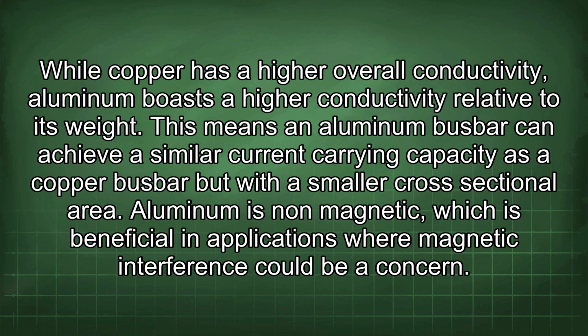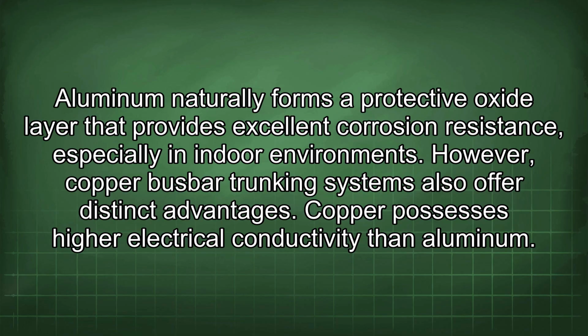While copper has a higher overall conductivity, aluminum boasts a higher conductivity relative to its weight. This means an aluminum busbar can achieve a similar current carrying capacity as a copper busbar but with a smaller cross-sectional area. Aluminum is non-magnetic, which is beneficial in applications where magnetic interference could be a concern. Aluminum naturally forms a protective oxide layer that provides excellent corrosion resistance, especially in indoor environments.